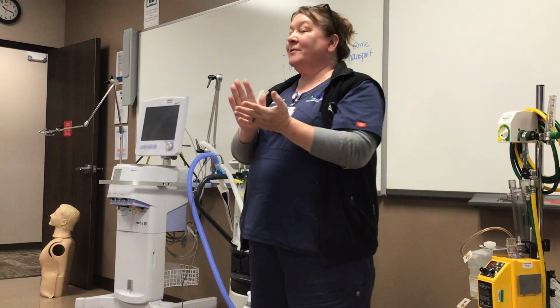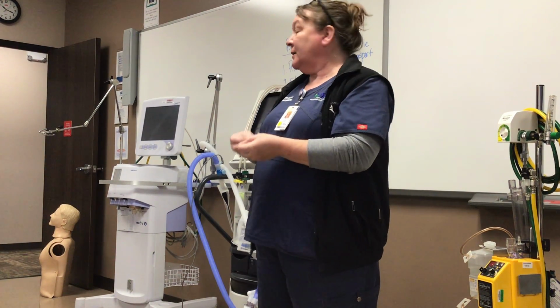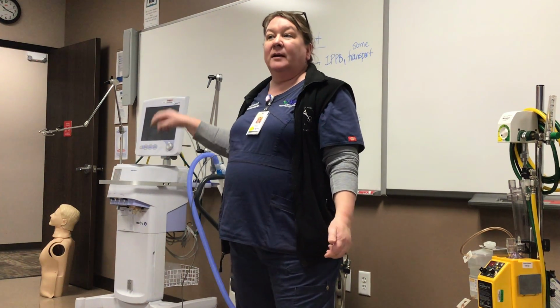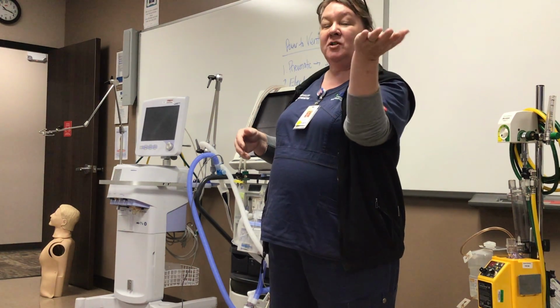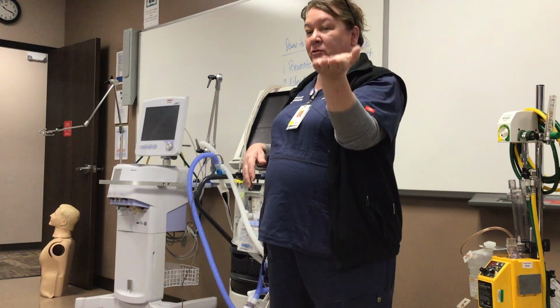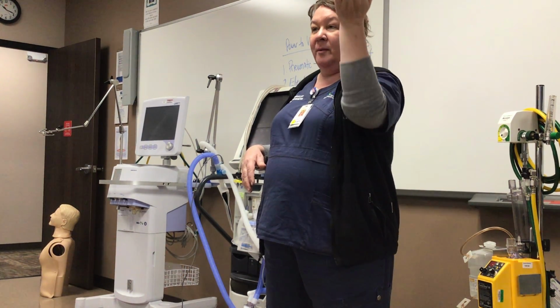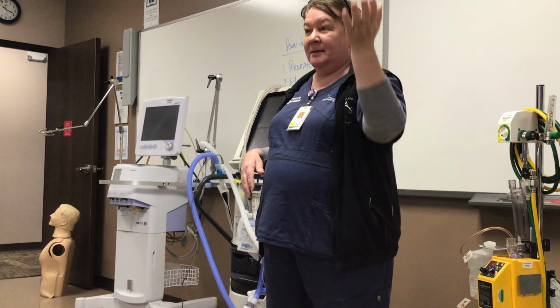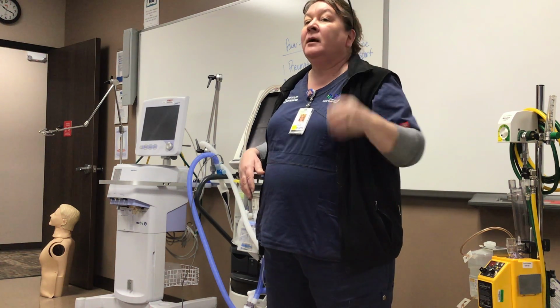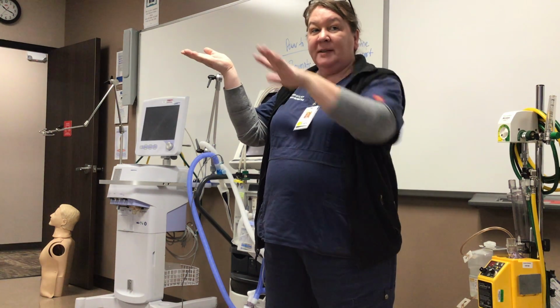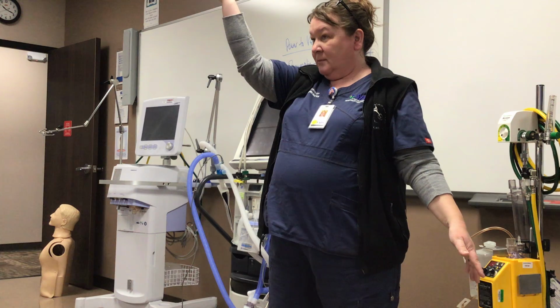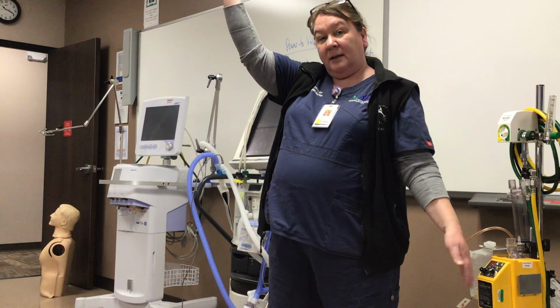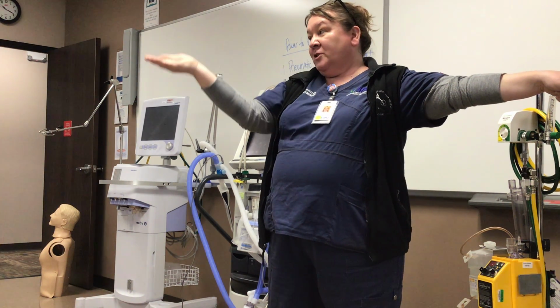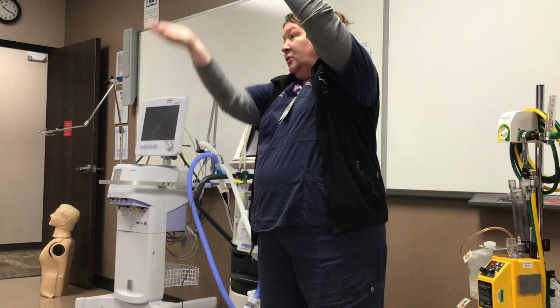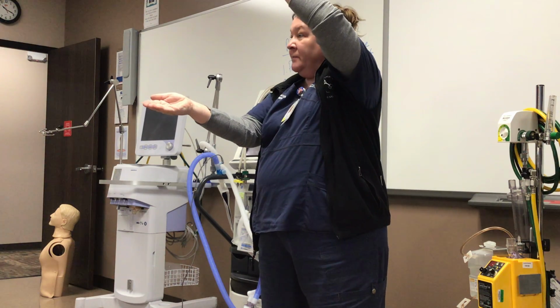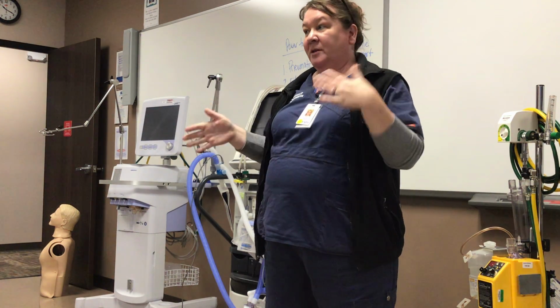The exhalation valve is a very important part of the ventilator. Some are connected to the circuit, some are external on the ventilator, some are internal on the ventilator. But your ventilator won't work if your exhalation valve doesn't work. The exhalation valve is simply a valve with a magnet that opens and closes, and it allows the vent to go from inhalation to exhalation. If that valve doesn't work, the vent can't deliver the breaths or stop the breaths, and it'll malfunction on you. During inhalation, when we're sending a breath to the patient, the exhalation valve closes so the breath can go to the patient. Then it opens during exhalation so the air can go back into the vent. Close, go to the patient, open, go back to the vent. Make sense? If that valve doesn't work, the vent can't cycle between inhalation and exhalation.